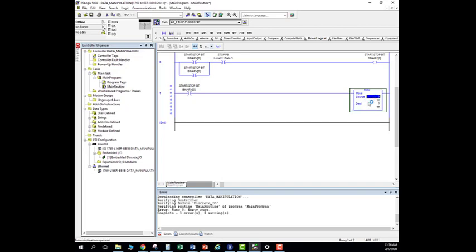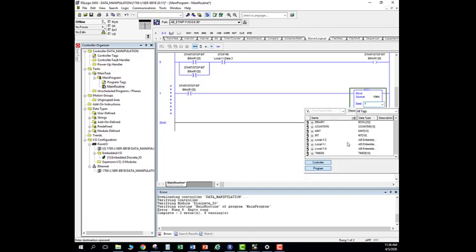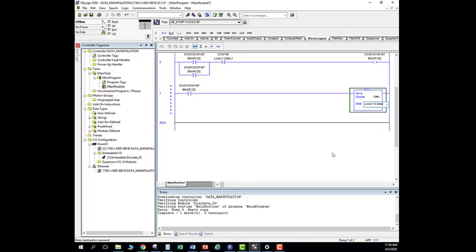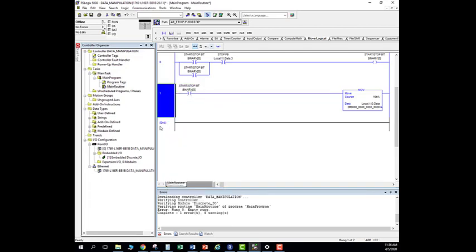For source one I can put a register or put a value in here. I'm going to put a hex value so I'm going to do pound sign — 16#A for the first value. Then I'm going to dump this right into the output data word — I'm going to dump it to the whole word, not one bit but all 16 bits of the output word.